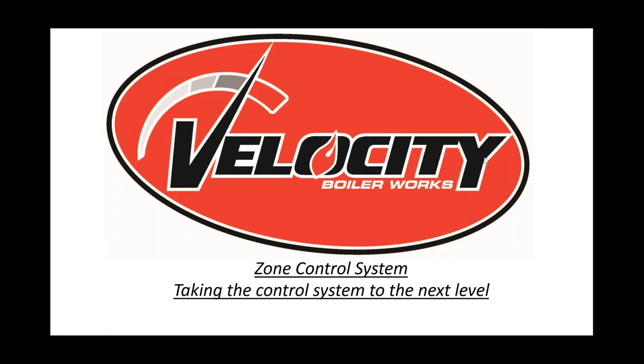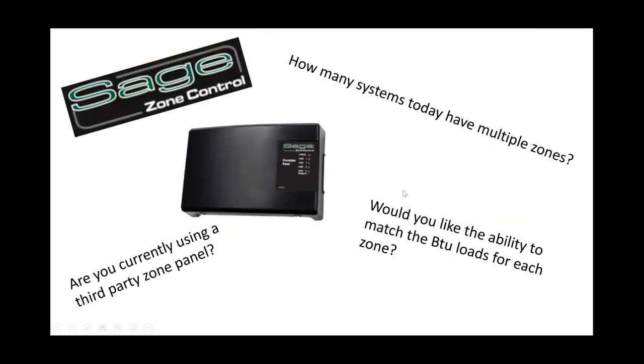So our Sage panel, again, is going to wire like a ZVC 504 or an SR 504 from Taco. Currently, we're the only one; no other competitor offers this. It really allows us to control the heating system, to fine tune everything with it. Most of our heating systems now have multiple zones, with Honeywell RedLink, and if you get really creative, you can zone almost anything if you can find the supply and the returns for that zone. And with PEX and everything, we can zone almost everything.